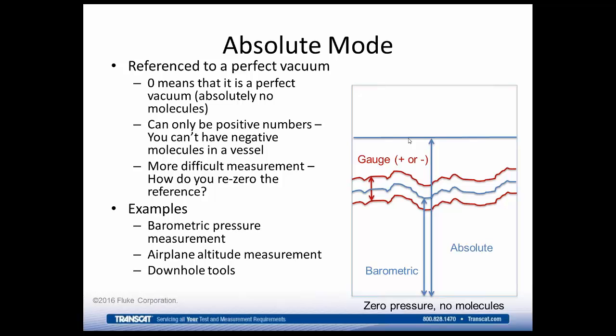Another example, in the oil and gas industry, are downhole tools. If you're measuring the pressure at the bottom of an oil well, you can't really reference that to atmospheric pressure. You can't open one side of your device up to atmospheric pressure because you're a few thousand feet below the ground. So the pressure measurement from a downhole tool is oftentimes an absolute mode measurement.